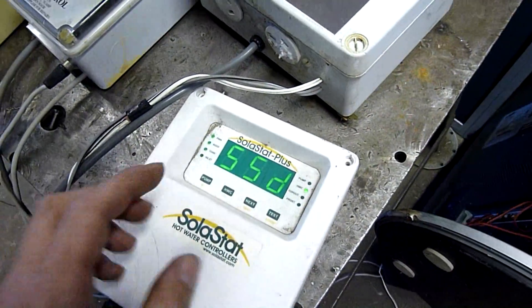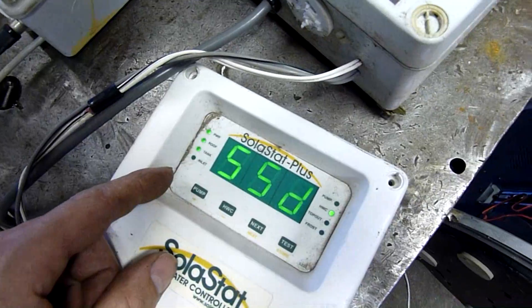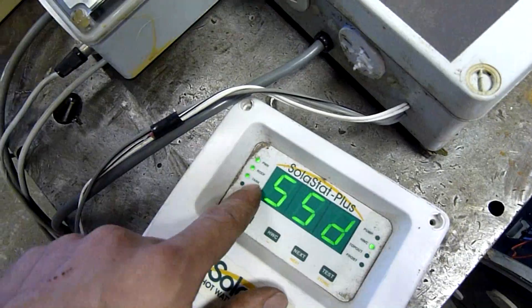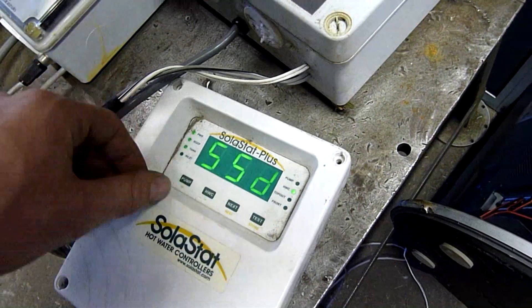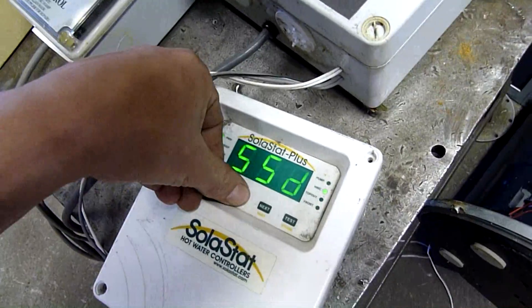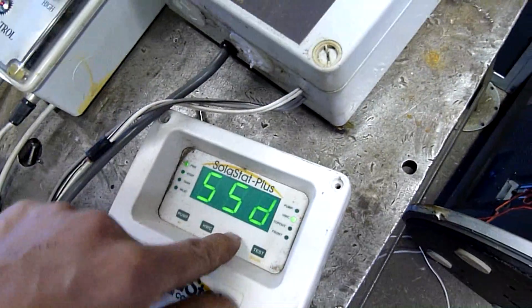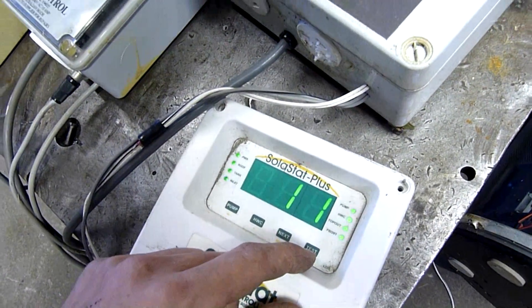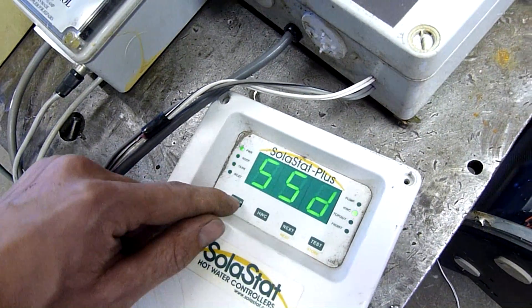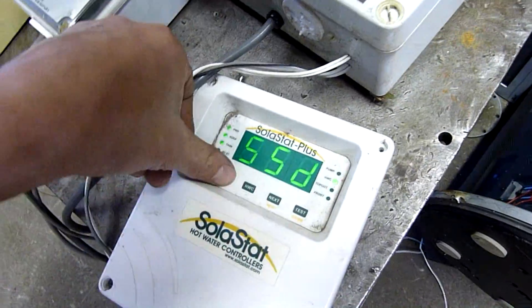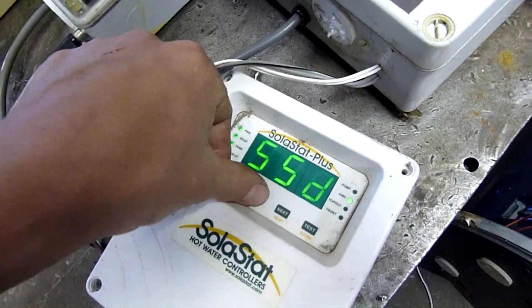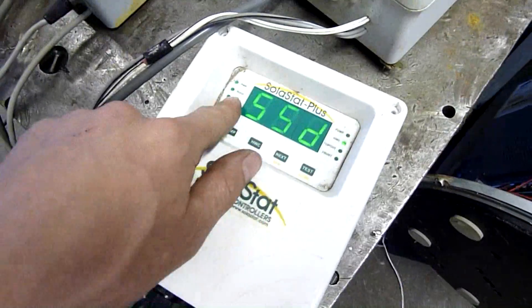This one here, what's it telling me? HWC is alright. That's probably indicating the roof and tank thermocouples are open circuit. So let's go HWC. Nope. Next. Test. Okay, pump relay works. I'm going to turn the pump on if it was connected. Next.